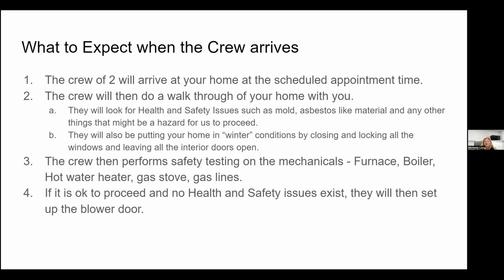After that, the crew performs safety testing on your mechanicals. If you have heat pumps and are all-electric, there's no safety testing needed, but for gas, oil, propane, or any combustion systems, we make sure there's no ambient CO, that the CO in the flue isn't high, and that it's drafting properly—all to make sure you're safe in the home.